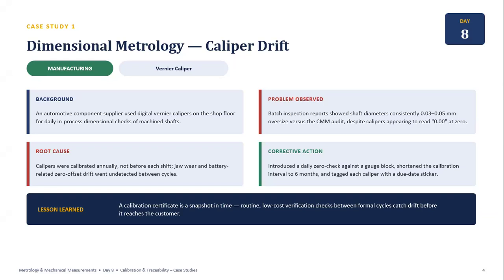The corrective action was to introduce daily zero checks using a gauge block, reduce the formal calibration interval to 6 months, and clearly identify the calibration due date on each instrument. The key lesson is very simple. A calibration certificate represents the condition of an instrument at a particular point in time. Routine interim verification is therefore essential for detecting drift before it affects the customer.